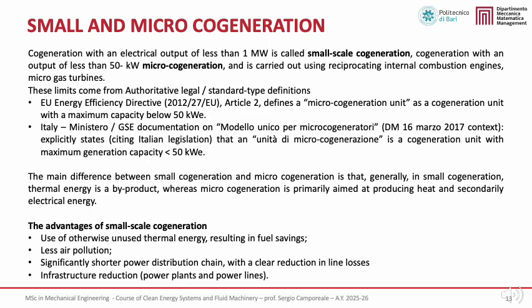In the previous slide, we classified cogeneration systems according to their electrical power output. We now focus on the lower power ranges, namely small-scale cogeneration and micro-cogeneration systems. Cogeneration plants with an electrical output below 1 megawatt are generally referred to as small-scale cogeneration. When the electrical output falls below 50 kilowatts, the system is classified as micro-cogeneration. These thresholds are not arbitrary, but originate from regulatory and standard definitions, such as those provided by the European Energy Efficiency Directive and by national regulations, including the Italian framework.